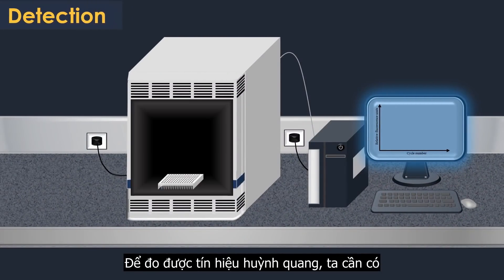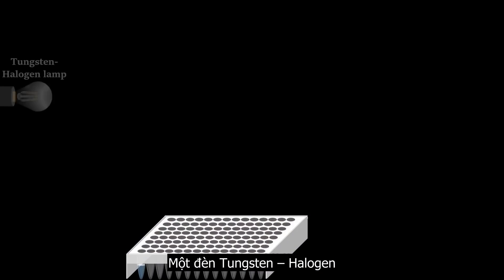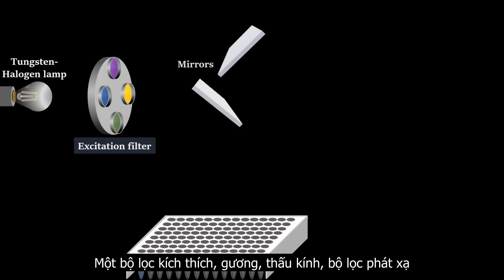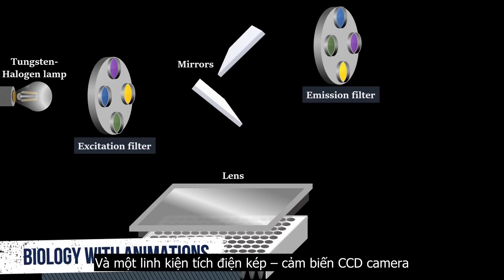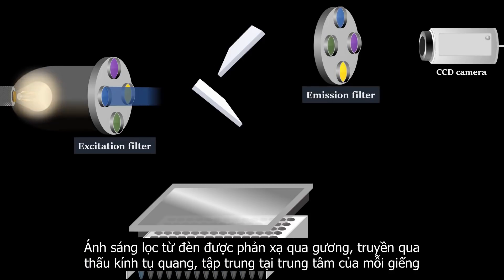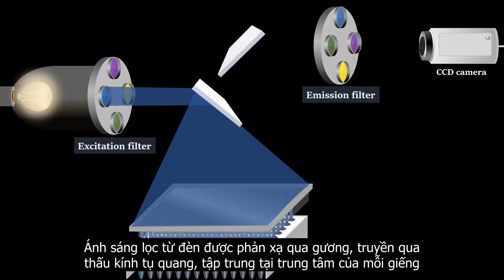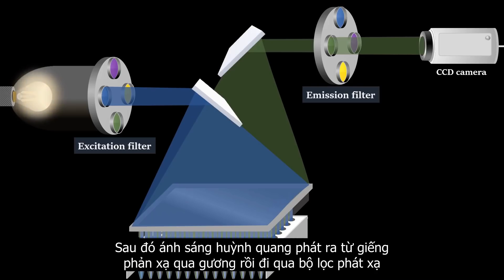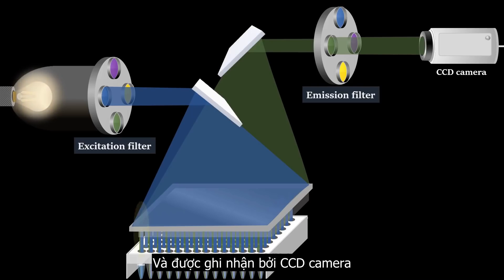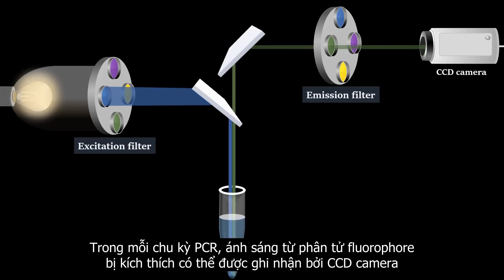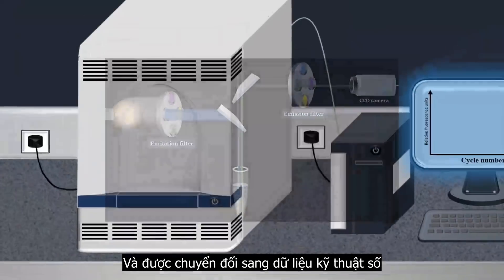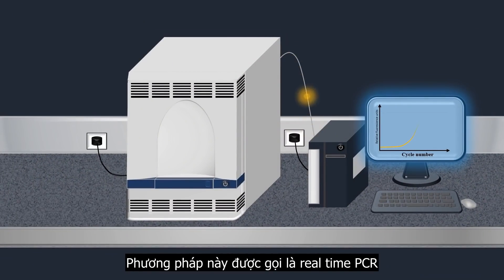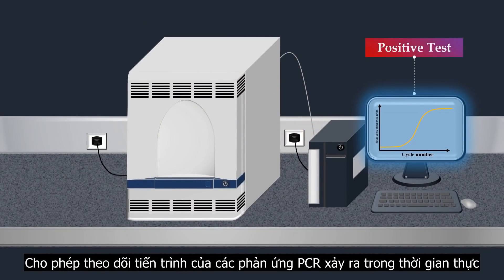For the measurement of the fluorescent signal, a tungsten halogen lamp, an excitation filter, mirrors, a lens, an emission filter, and a charge-coupled device (CCD) camera are used. Filtered light from the lamp is reflected off a mirror, passes through a condensing lens, and is focused into the center of each well. Then fluorescent light emitted from the wells reflects off the mirror, passes through an emission filter, and is detected by the CCD camera. In each PCR cycle, light from excited fluorophores can be detected by the CCD camera, which converts the light it captures into digital data. This method is known as real-time PCR, which allows monitoring of the progress of the PCR reaction as it occurs in real-time.